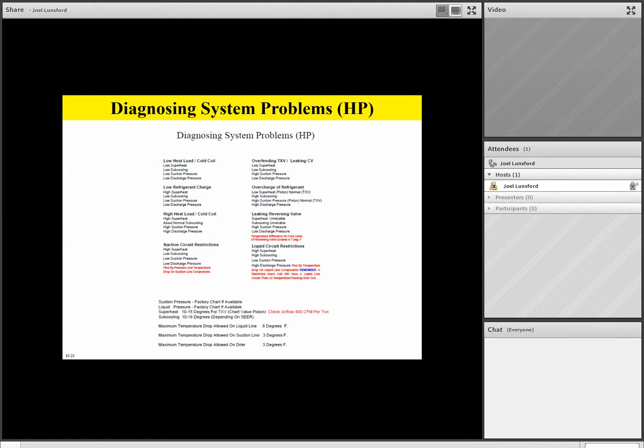Now, team, always remember too that if you have low superheat or if you're having issues with airflow on the indoor coil, especially in the cooling mode of operation, that can affect system performance. So always check your airflow, make sure both coils are clean, your outdoor coil and your indoor coil, before you do any of these diagnostic procedures, and make sure that airflow is 400 CFM per ton of cooling on that indoor coil in the cooling mode.